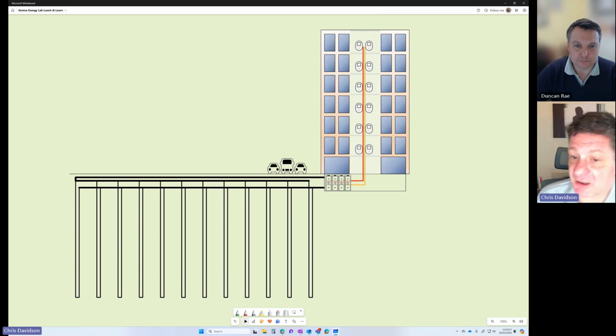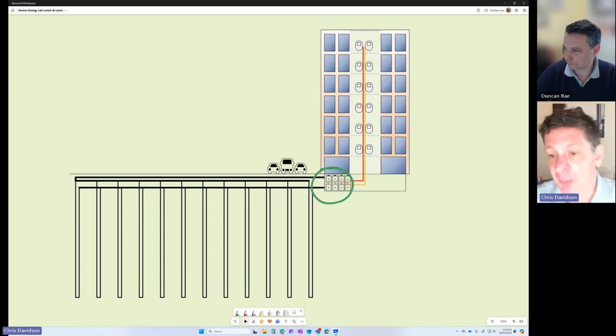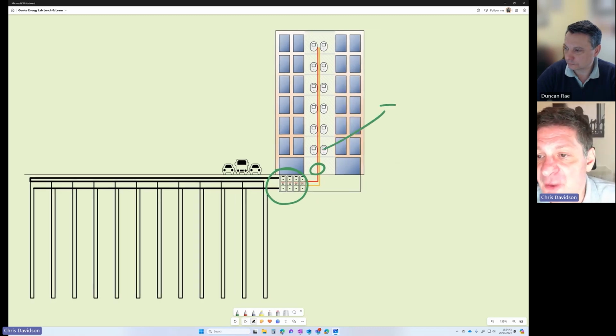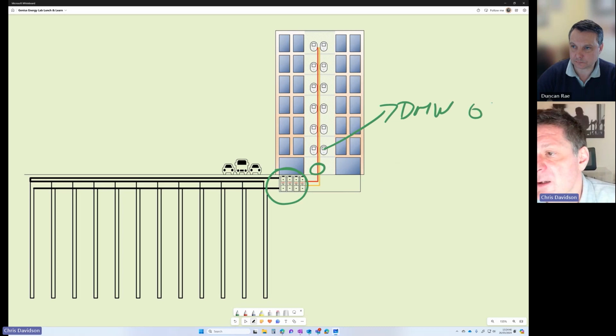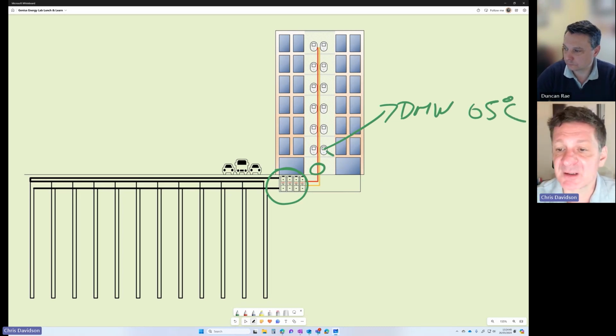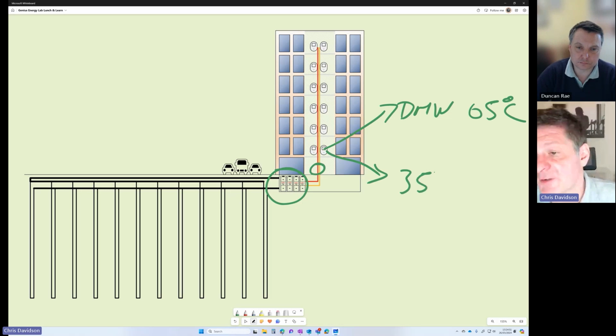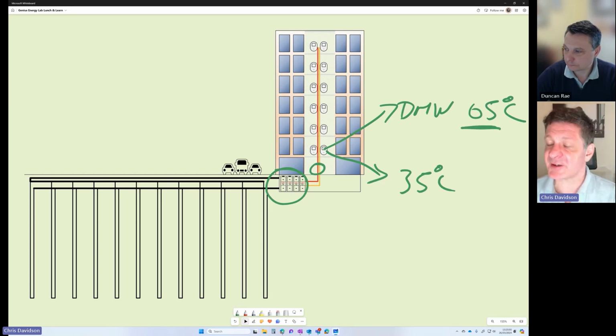Let's look at a conventional central plant district heat network fed by ground source. We've got plant down here, heat pumps in the basement, delivering heat up a high temperature, well-insulated riser, which goes into a heat interface unit in each dwelling. That heat interface unit delivers domestic hot water, let's say at 65 degrees C, and could deliver space heating as low as 35 degrees C. But we've only got one riser, one mechanism for taking heat up the building, so we have to deliver heat at that higher temperature. That's the only option we've got, so we're delivering heat at 65 degrees C.